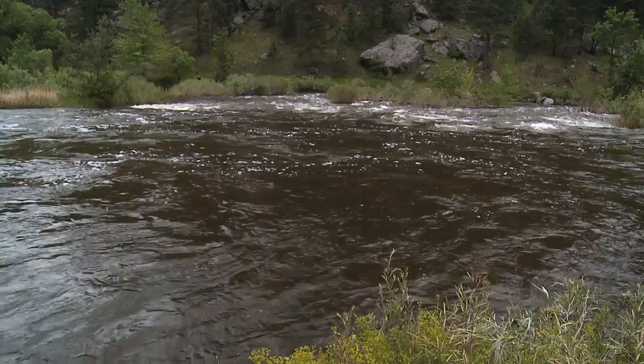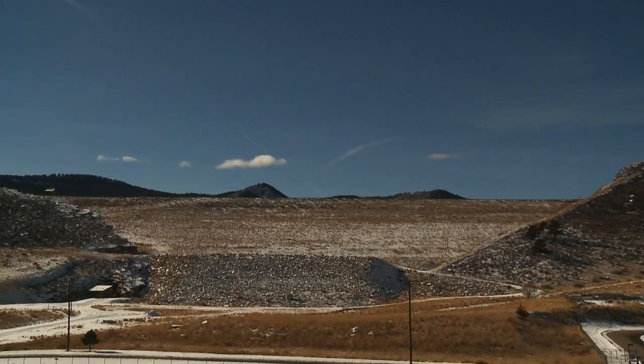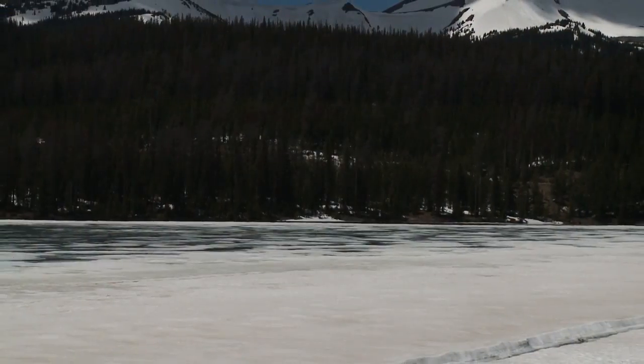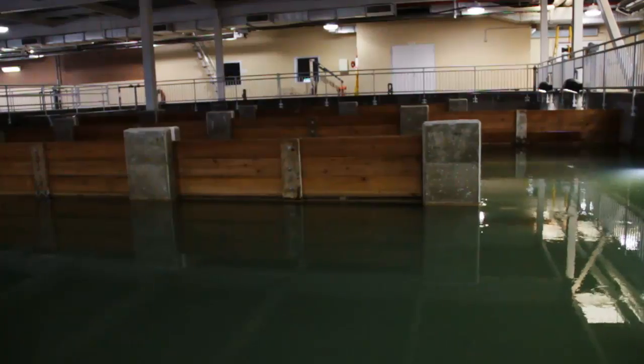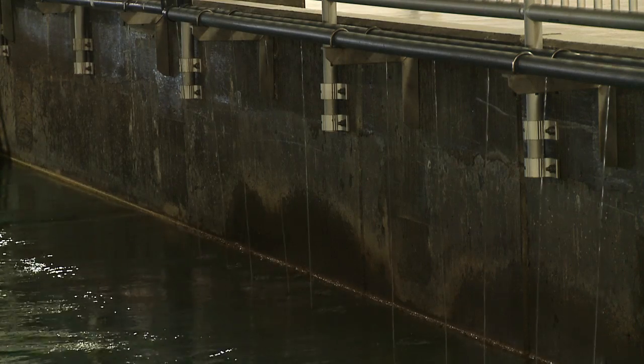From there, it goes to the water treatment plant west of Fort Avenue. The raw water from the Poudre River travels about 8 miles through a series of pipelines to the main city plant. We blend water from Horsetooth Reservoir and the Poudre River to take advantage of the best incoming water quality from each source. The raw water quality changes dramatically throughout the year, presenting unique challenges to producing consistently high-quality water that our customers depend on. The blended water is mixed with coagulation chemicals that help the dirt and silt stick together to form larger particles through the flocculation, or mixing, process.